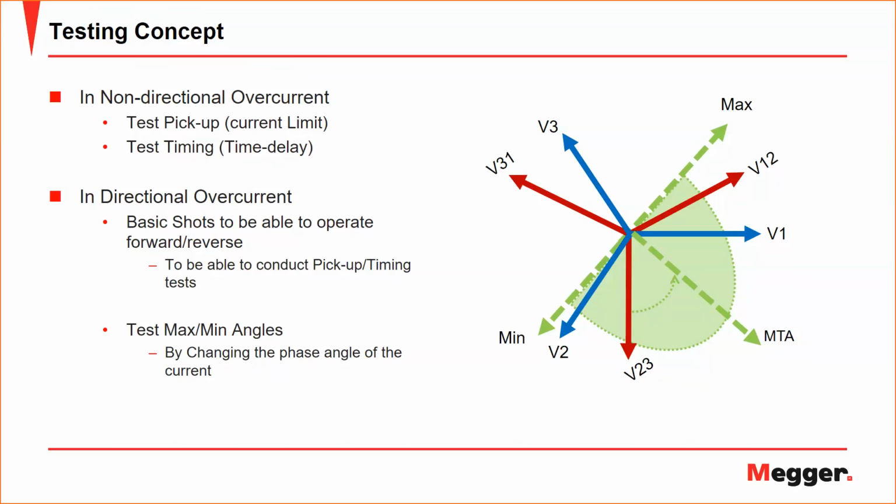And if you want to test the directional element itself, you can test it by testing the maximum and minimum angle by changing the phase angle of the current to see at which angle exactly it will operate the relay.